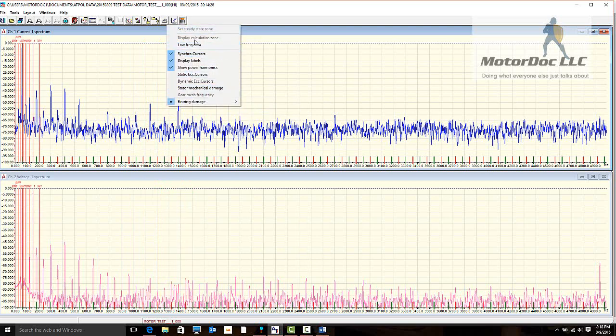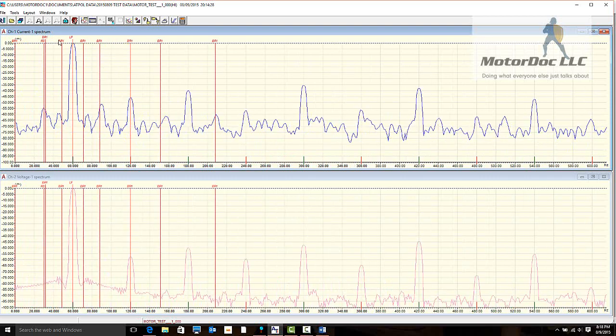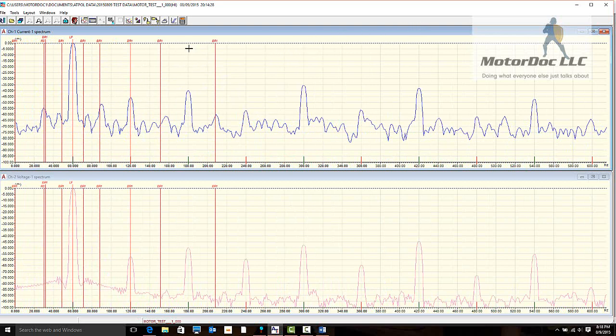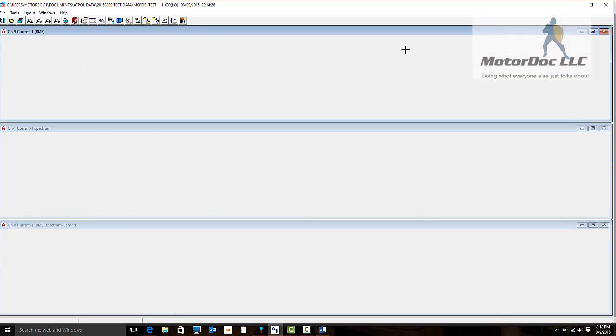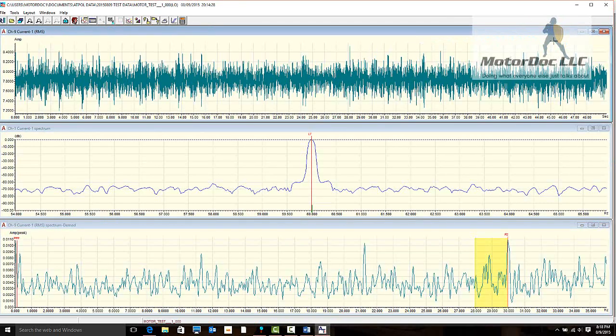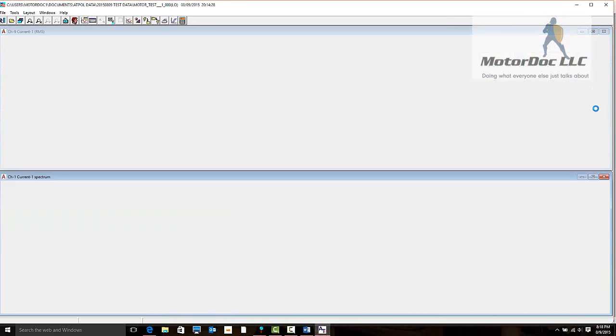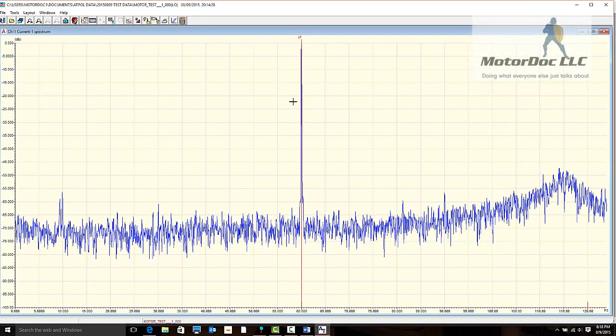Any type of bearing-related frequencies, which we can take a look up here or go in the other data. However, those fall right on some line frequency peak, so chances are this is not that. We do know that one bar has been milled out on these. Let's go back to our low frequency data and let's take a look at something else that's a feature in this particular software. This will allow us, especially in variable speed, variable torque, and VFD applications, to look at a couple of additional things.